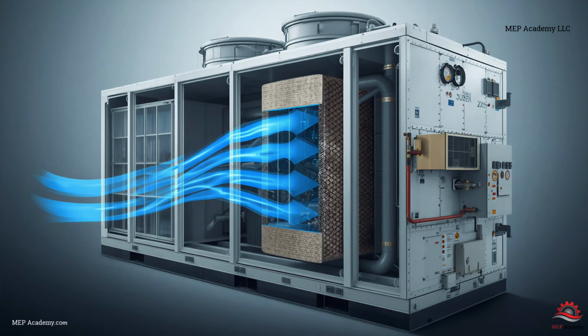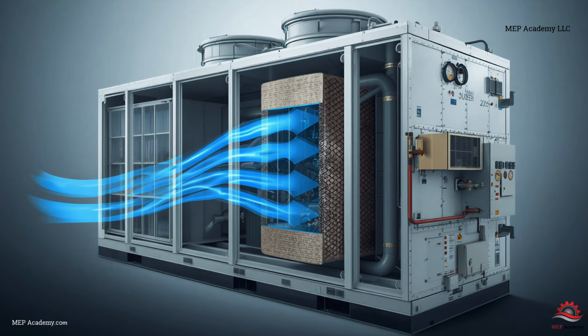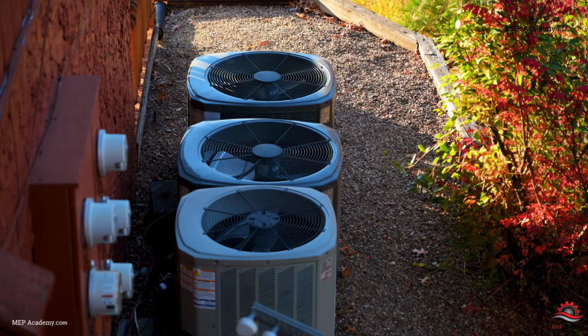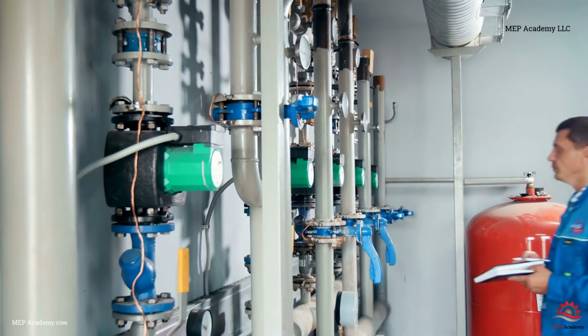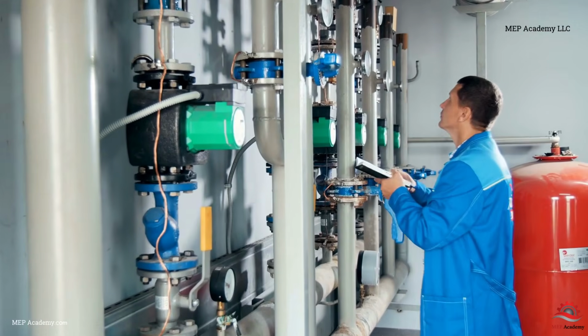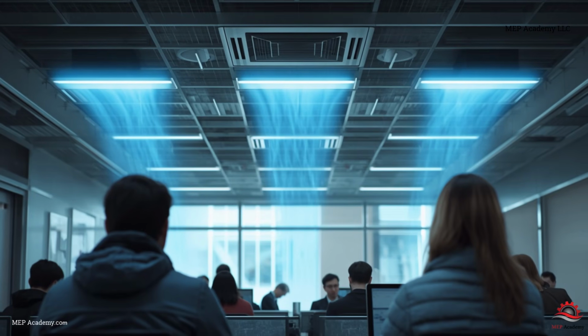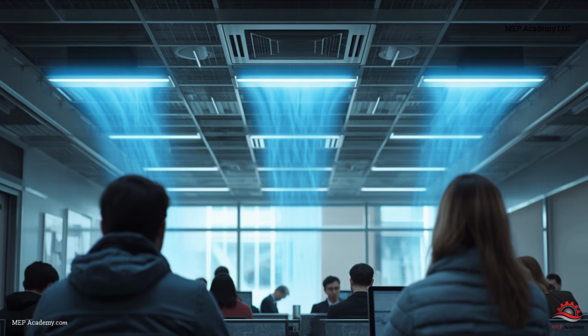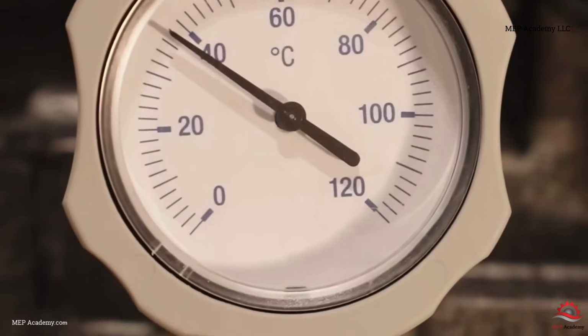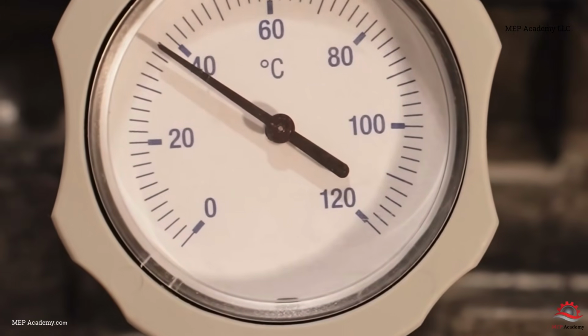The solution is to measure airflow instead of guessing. Verify fan performance. Measure static pressure. Inspect dampers. Review duct sizing and ductwork for leaks. Confirm terminal units are operating correctly. Airflow measurements often reveal problems that temperature measurements alone cannot identify.